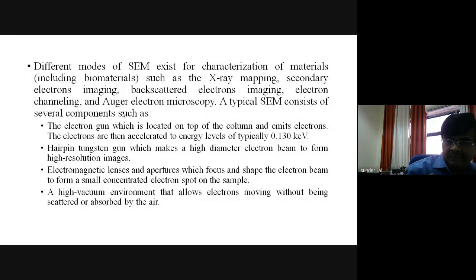Electromagnetic lenses and apertures focus and shape the electron beam to form a small concentrated electron spot on the sample. A high vacuum environment allows electrons to move without being scattered or absorbed by the air. This is the basic requirement of SEM. SEM should have a high vacuum environment that allows electrons to move without being scattered or absorbed by the air.